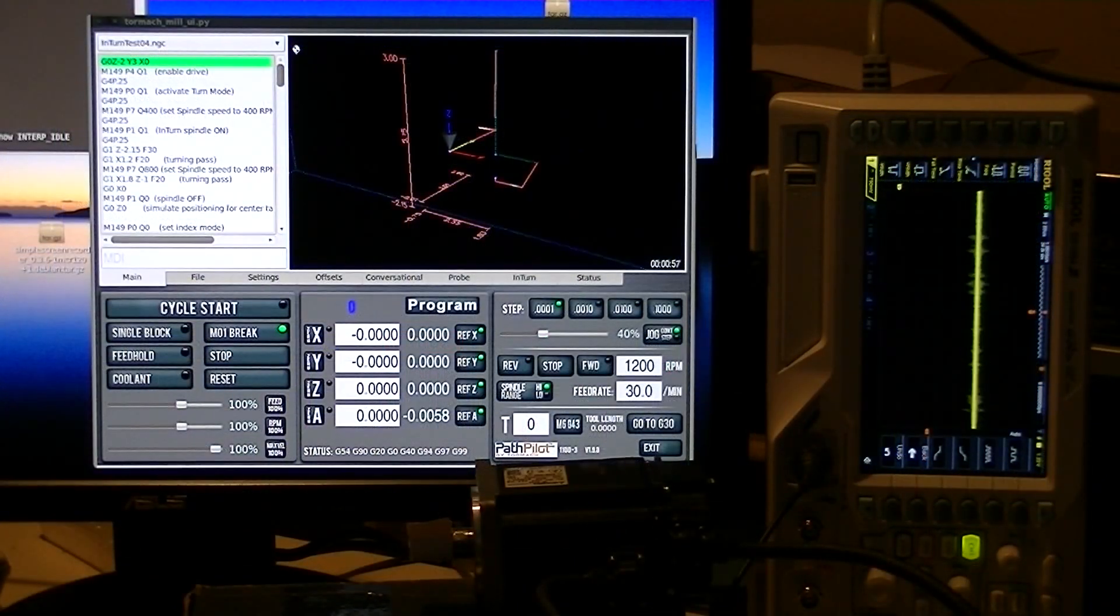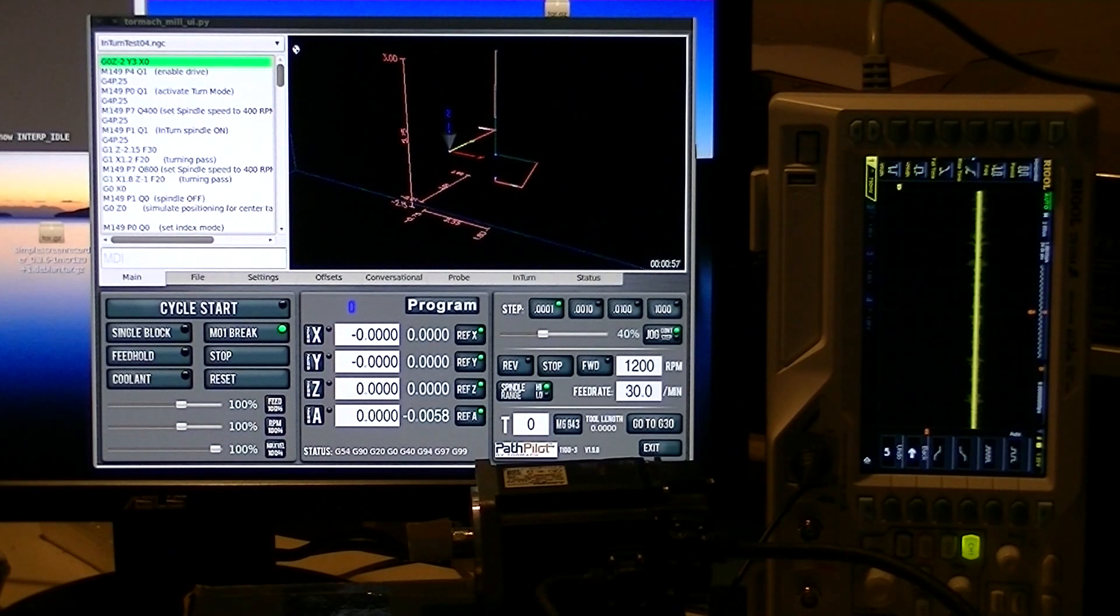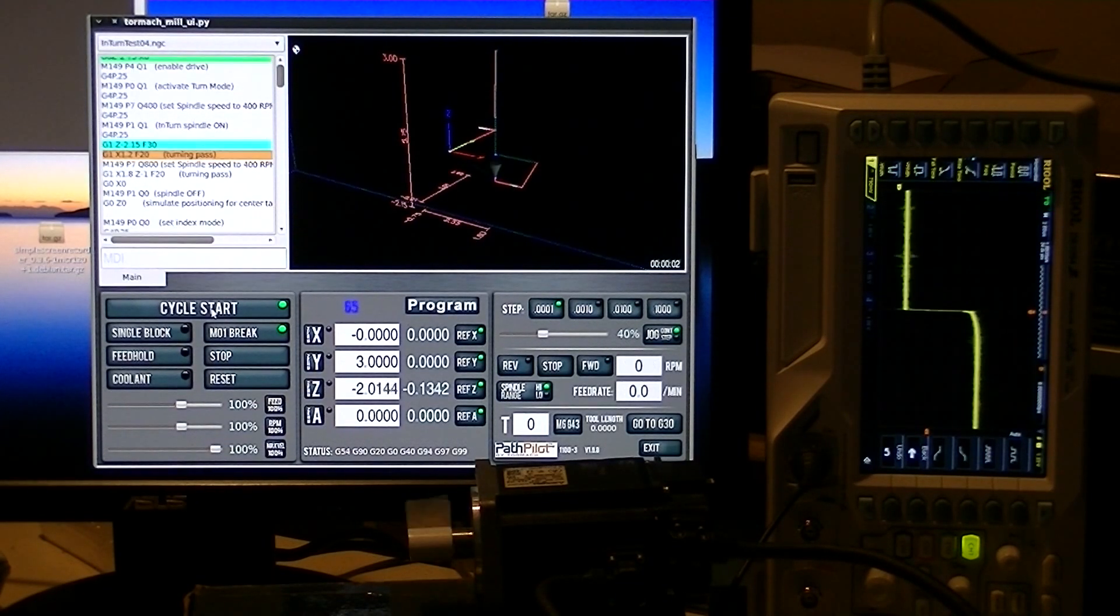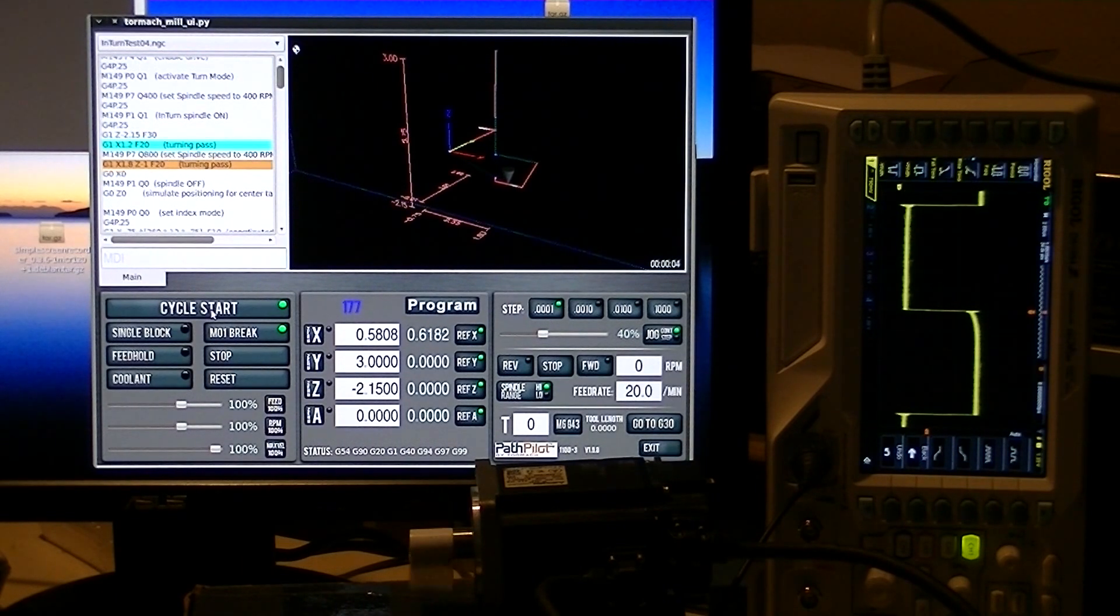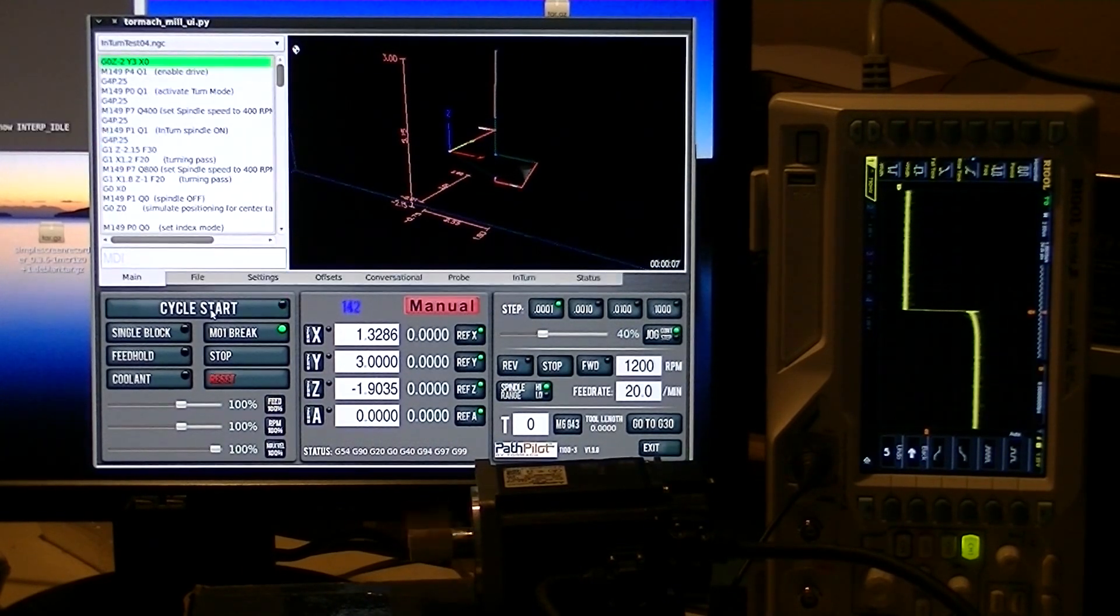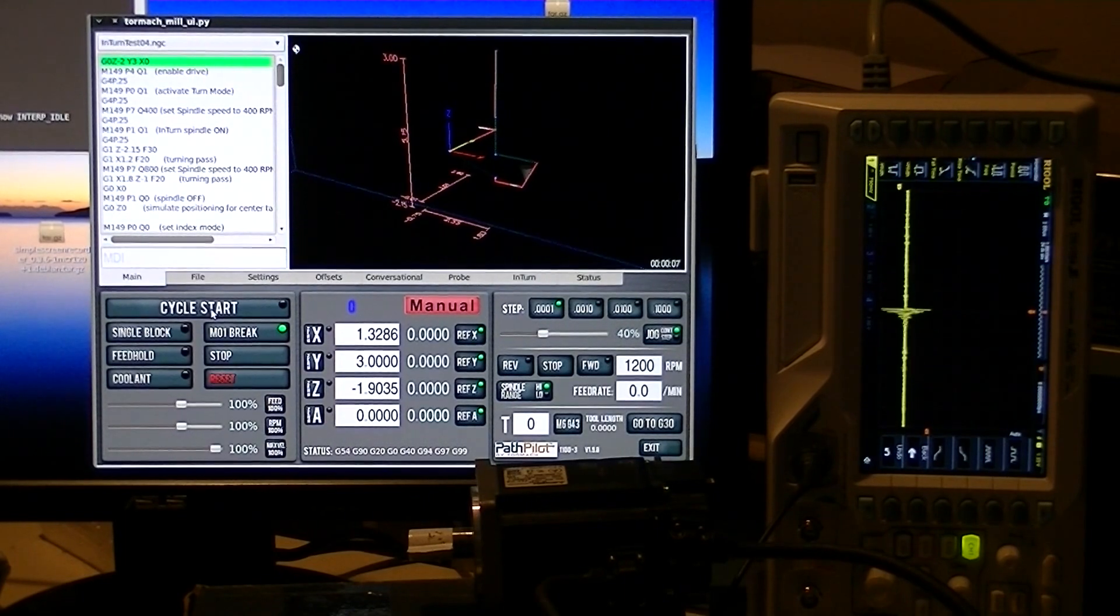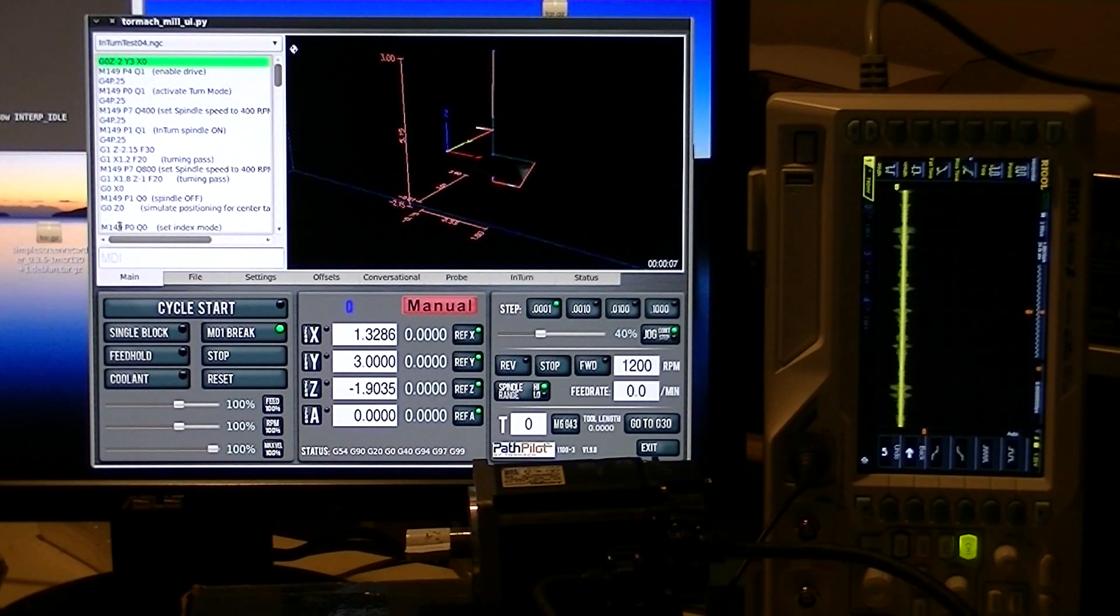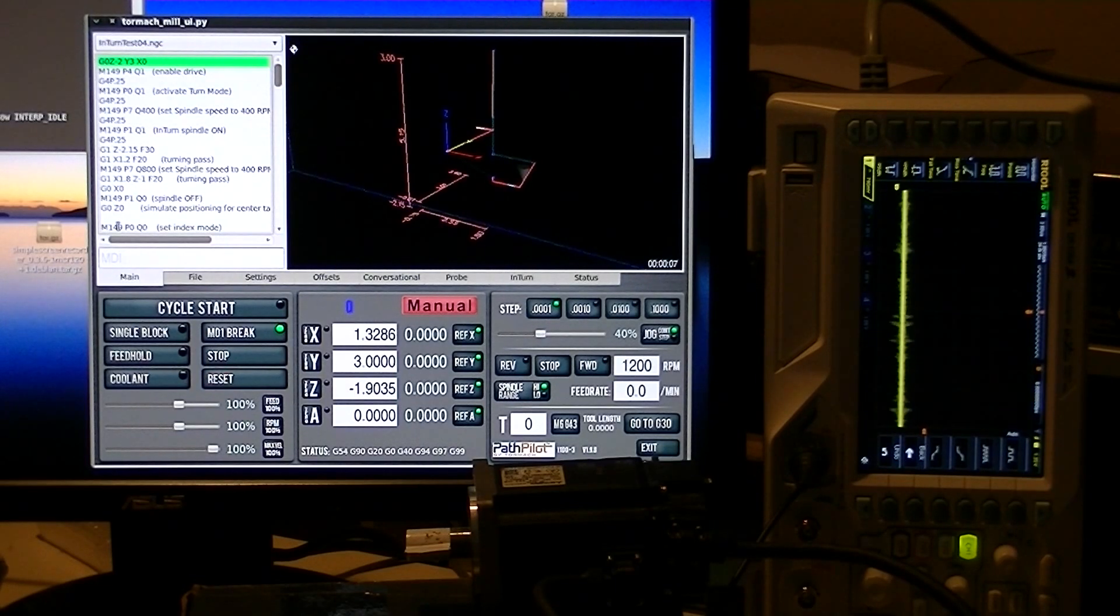Okay, the last thing we want to demonstrate is how the system reacts to an emergency stop. While the motor is running, I'm going to force an E-stop by disconnecting the alarm line on the drive.